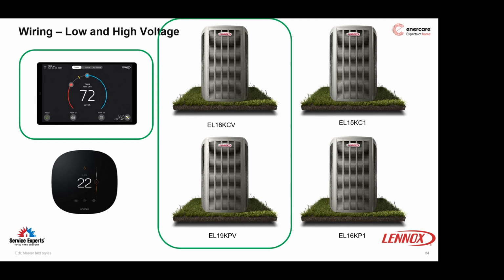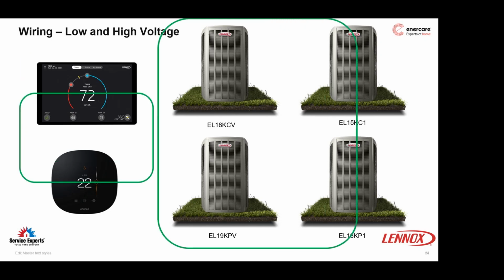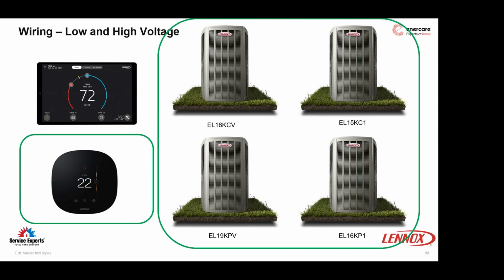It's a complete 4-wire system, R, C, I-, I+, connections on all of the equipment, indoor and outdoor, if they're fully communicating. But there is also this lovely 24-volt thermostat. Pictured, I chose the Ecobee 4. It happens to work with all of them, which is actually kind of nice. Lennox, I don't know if they've just been pressured into it or finally figured out that not everybody is going to buy their communicating equipment, so their communicating equipment needs to work with all of the thermostats available, or most of the thermostats available in the marketplace these days.